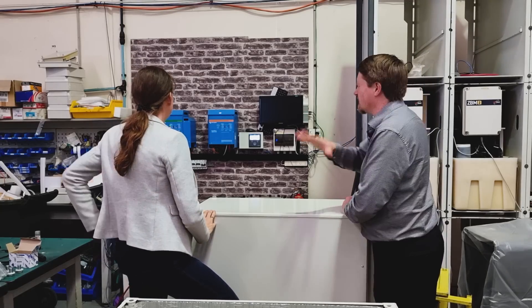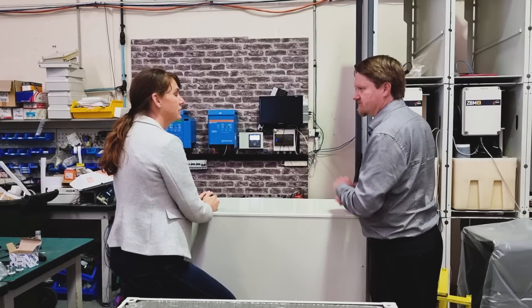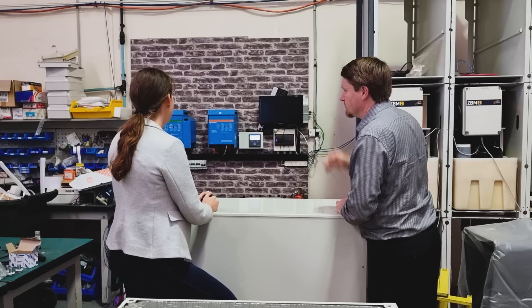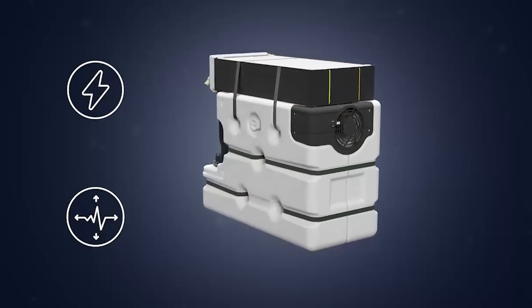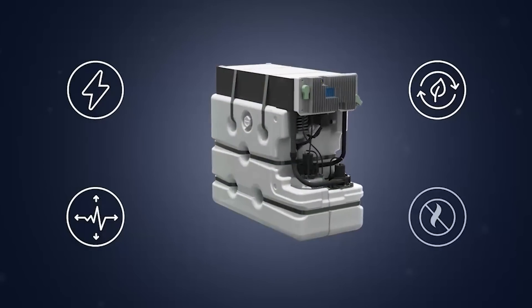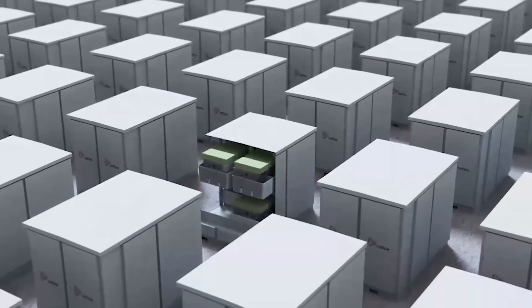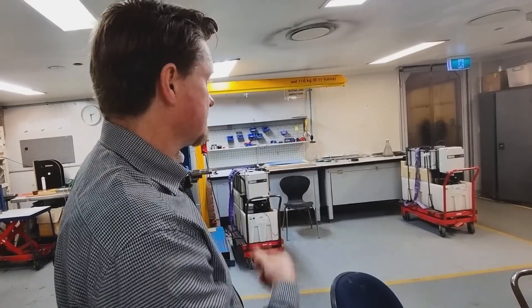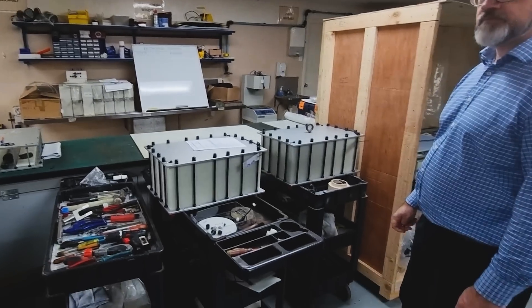This is where we're doing some more real-world testing. The long duration testing in the lab is done at 48 volts, which is the native voltage of the battery. Here we're actually connecting the batteries to inverters, creating AC electricity out of them and running them through different types of loads. Redflow have had some of their batteries out in the field for years, with some at the end of their lifetimes. We have a complete recyclability path and plan for the entire battery — no heavy metals, no lead, no toxic chemicals, nothing that will break down into a toxic chemical. We still receive batteries back that are disassembled and analysed in our labs, then repurposed — we get separate stacks and restack a battery to increase its longevity.